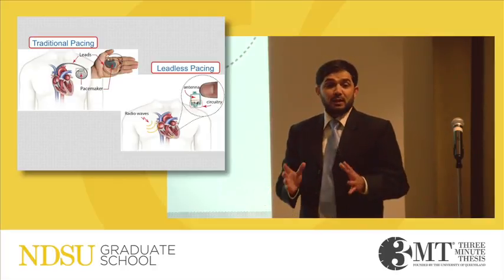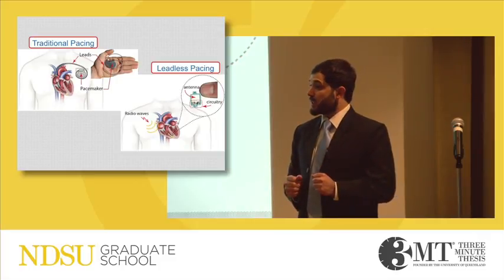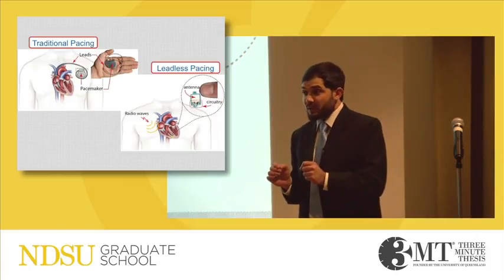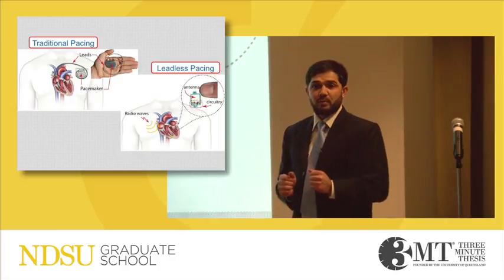So the question is: how do we eliminate these problems — the batteries, the leads, and all these associated complications? This is where my research comes in. The goal of my work is to develop a novel, tiny pacemaker that can be fitted directly inside the heart, not on the chest anymore.